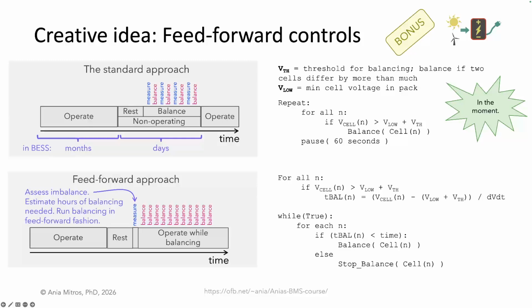For every cell, we evaluate whether it needs balancing. We estimate T-bal, the amount of time needed to balance the cell. What I have here as dVdt is a shorthand. Since the voltage curve is not linear, accurately estimating the time needed to balance is a little more complicated than this equation. And then we put the system back into operation and balance for the planned length of time. This algorithm has us make a plan and then execute the plan in a feed-forward manner.